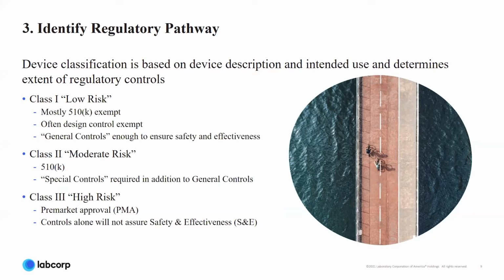The class 2 moderate risk ones are usually where a 510(k) submission is needed, where there's probably something already on the market that you can say you're just as safe and effective as, and that's usually what you would use as a predicate device to be able to submit a class 2 device. And there's sometimes special controls that are required, and we'll get into that more in just a little bit.